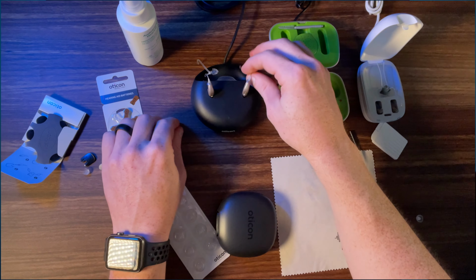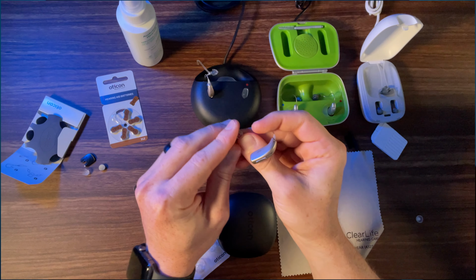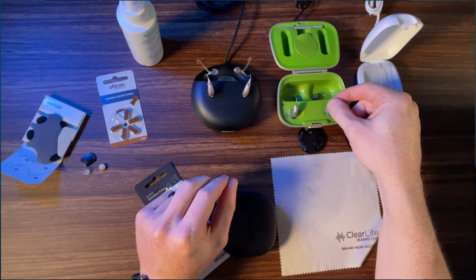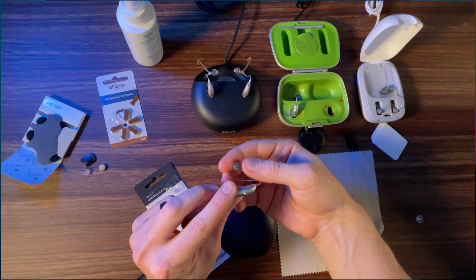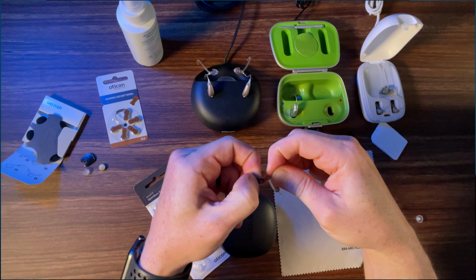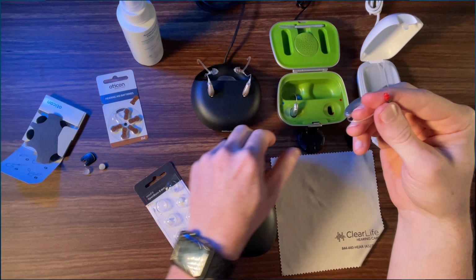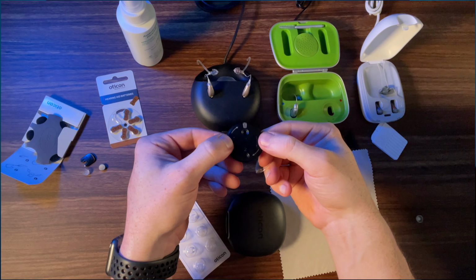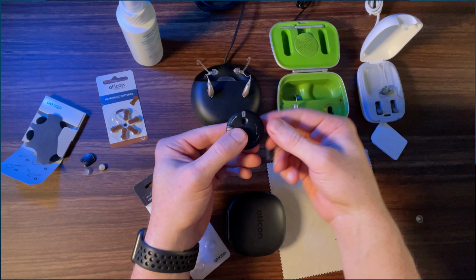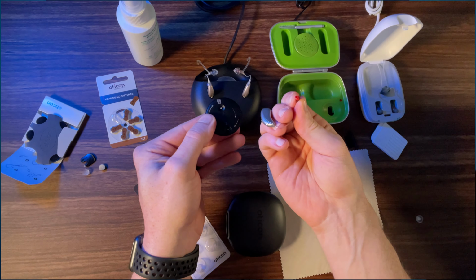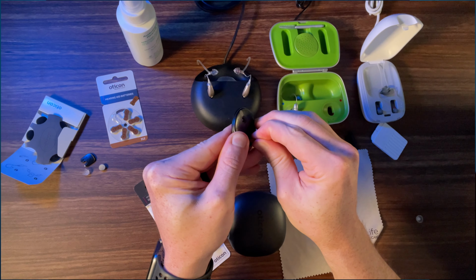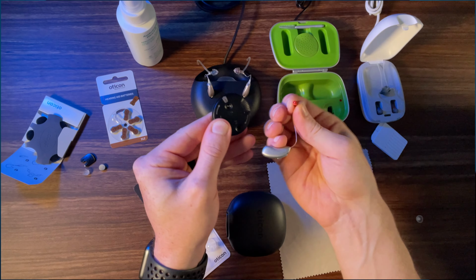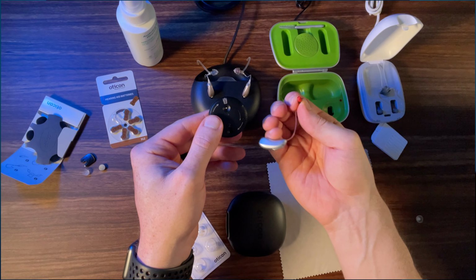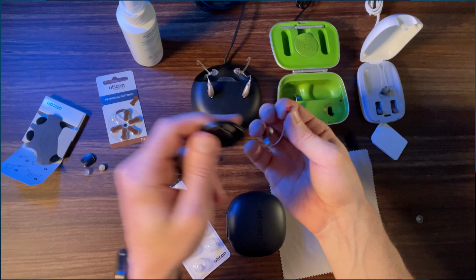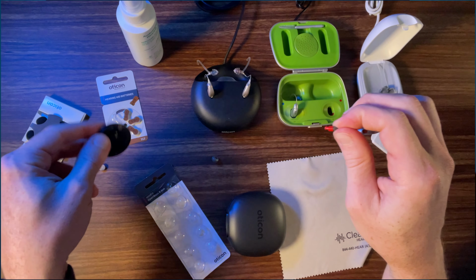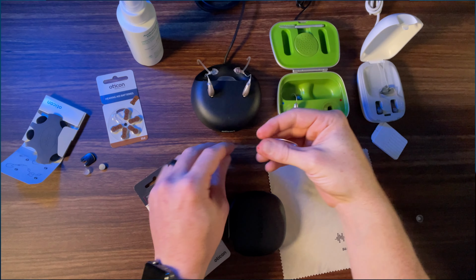Of course, after you do that, you do want to put the dome back on. Phonak has a little bit different system, which I'm not a huge fan of. They've got this wheel, so you have a little trash can on one and then a replacement wax guard on the other. So you stick the hearing aid into the trash can end, pull out the old one, and snap in the new one. And what can happen with the new one is it can get stuck and kind of wedged in funny, and then your speaker now has a filter wedged into it crooked. So you want to make sure you put it straight in, straight out with the Phonak. And then of course we're going to put our dome back on.